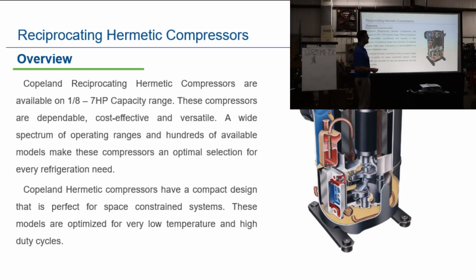So this is the CR, these are our A, our Cs, and it'll be up here in a second. I don't remember off the top of my head. So these are hermetic compressors. You cannot service these ones, right? So if something fails, you can't pull them apart like a semi-hermetic compressor. We have a discharge line through the oil, and what do you think we do that for? Why do we design it like that? Oil flow, keeping oil in the bottom.